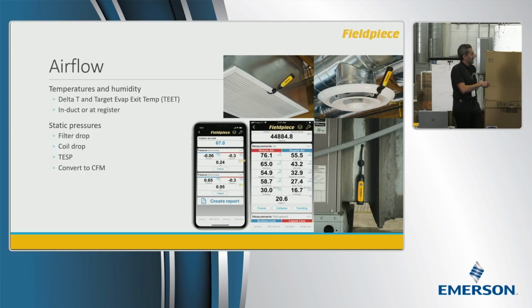We can check pressure across a filter drop, pressure on one side, pressure on the other side. Although typically, we can see when a filter is dirty, right? But we could also do that. There's some other usefulness in measuring the pressure drop across your evap coil. But one of the most common ones is a target external static pressure. And what's useful about a target external static pressure measurement is that the manufacturer sets a value at which that equipment should operate. So typically, they set the value at 0.5 inches of water column.